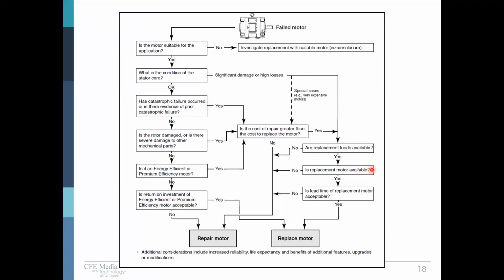Is the replacement motor available? The new motor is available in stock at a supplier, or the new motor is 2 weeks away, but the application is such that it can be down for 2 weeks. So that would still be a yes. We move to lead time, and again, if that 2 weeks was okay, then we move down and say replace the motor. What about if there's significant damage, but it's a special motor? We've got that 1,000 horsepower motor. That's probably not on anyone's shelf. So we say, is the cost of repair greater than the cost to replace the motor? If it is, we move into replacement mode. If it's not, then we move down into repair the motor mode.